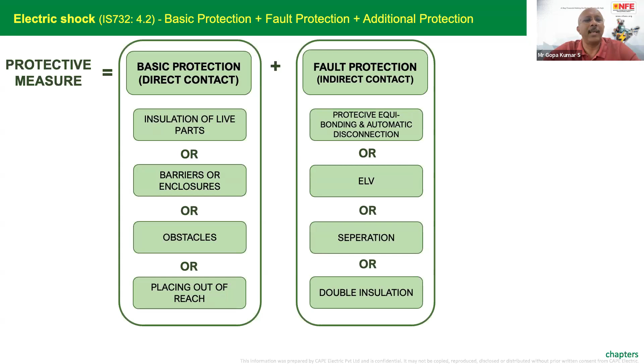In case of failure of basic protection, we go to a fault situation. Fault means there is no basic protection; the basic protection has already failed. Earlier, we used to call this protection against indirect contact. Indirect contact means there is some insulation failure or some fault, as a result of which a person may get electrocuted. The identified safety measures are, number one, protective equipotential bonding and automatic disconnection of supply; then extra low voltage, electrical separation, and double insulation. These are the identified safety measures for fault protection. You can also have an enhanced protection, which gives the properties of basic plus fault protection. In case of failure of basic protection and fault protection, you need additional protection. Example: a 30 milliampere RCD is an additional protection.